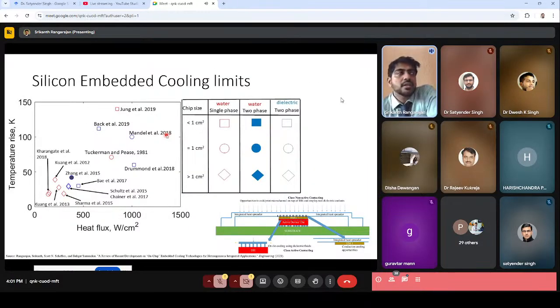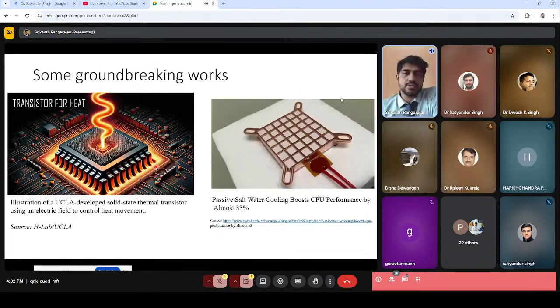The next emerging area is silicon embedded cooling. When we embed cooling technologies directly onto the silicon, we can reach more than 1,000 watts per square centimeter. Literature from Drummond et al., in collaboration with IBM, demonstrated removal of 1 kilowatt per square centimeter of heat, compared to the 790 watts per square centimeter achieved by Tuckerman and Pease in the past. Today we're seeing literature discussing more than a kilowatt per square centimeter. We want to push the paradigm and cool even more, so we need to look further into phase change material based cooling.